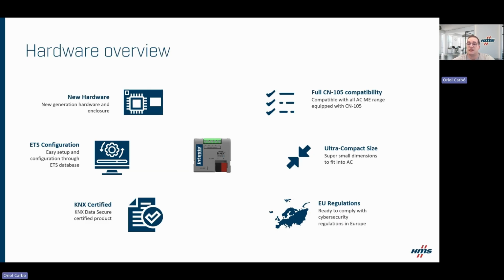And the gateway is KNX Data Secure certified, as I said before, which means secure communication is built in at protocol level, not added as an external layer. So it's also designed to be ready for European cybersecurity regulations, so it fits both current and future compliance requirements, which is pretty important. Despite being a new platform, it remains fully compatible with the CN105 connector, so it works with the full Mitsubishi Electric HVAC range equipped with this connector. Overall, this hardware combines compact design, standard ETS configuration, KNX Secure certification, and full Mitsubishi Electric compatibility.